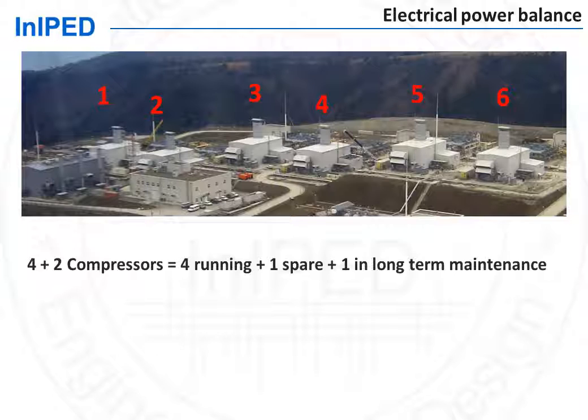This means four compressors are running, one is spare in hot standby, and one is available for long-term maintenance. What shall be the maximum power consumption considered for the compressors? It is not six times the consumption of one compressor, nor four times. Indeed, when one compressor has to be taken out of service for maintenance, to ensure that the plant duty is still met, operations need to put a fifth compressor online before the compressor is taken out for maintenance.